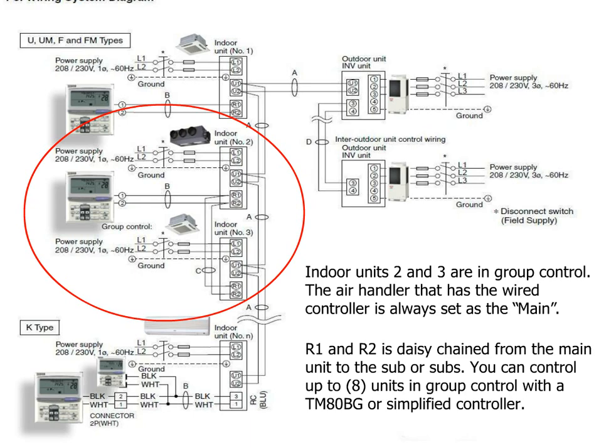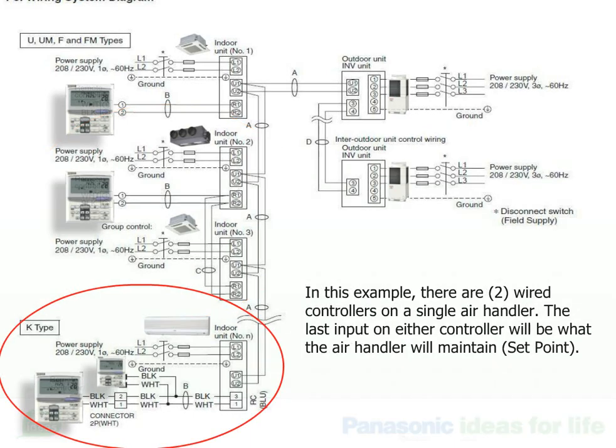The air handler that has the wired controller is always set as the main. R1 and R2 are daisy chained from the main unit to the sub-unit, or units. You can control up to 8 units in group control with a wired controller. In this example, there are 2 wired controllers on a single air handler. The last input on either controller will be the command that the air handler will follow.